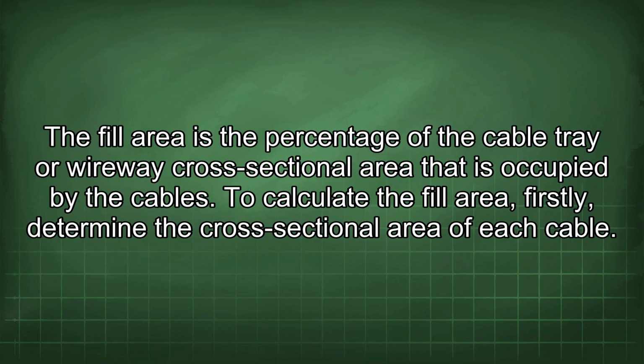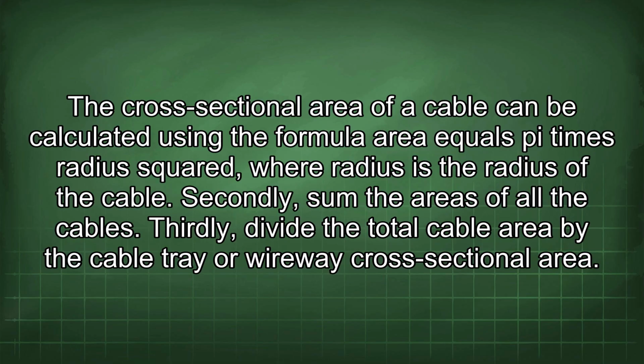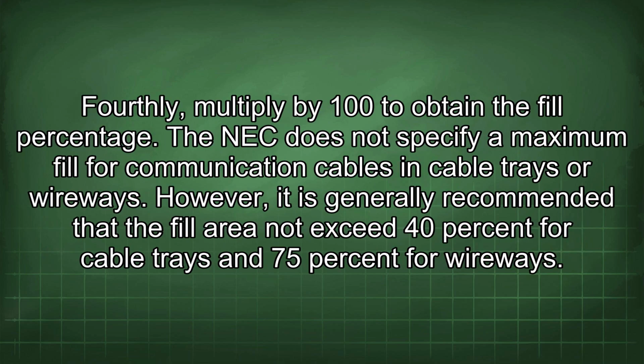To calculate the fill area, firstly determine the cross-sectional area of each cable. The cross-sectional area of a cable can be calculated using the formula area equals pi times radius squared, where radius is the radius of the cable. Secondly, sum the areas of all the cables. Thirdly, divide the total cable area by the cable tray or wireway cross-sectional area. Fourthly, multiply by 100 to obtain the fill percentage.